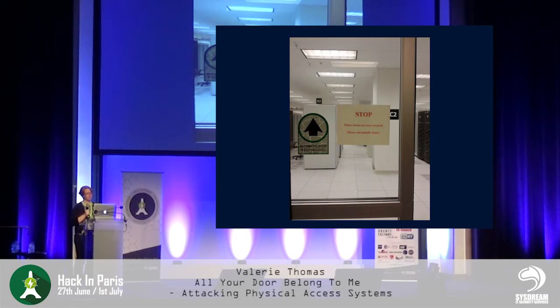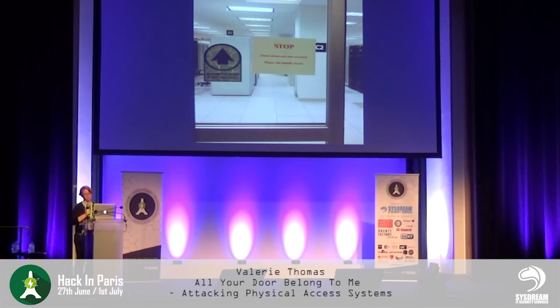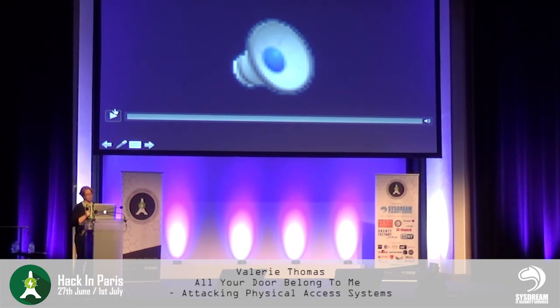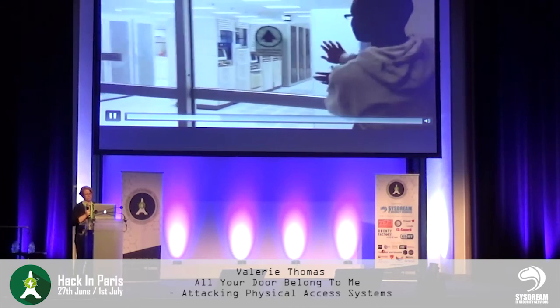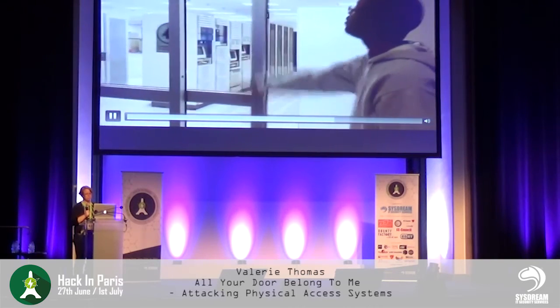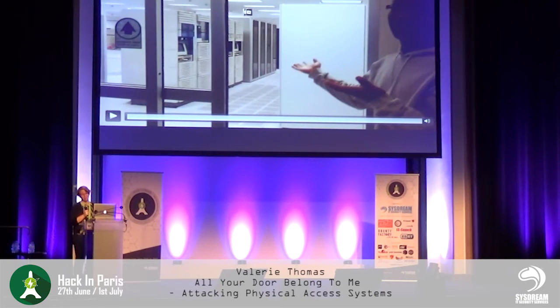We had a client that installed these types of doors on their pre-production data center because they thought it would be easier for the techs to get in and out with their carts and things without having to worry about holding the door. It's set up to comply with the fire code in the States, but they kind of forgot to make some adjustments to it. So you don't actually have to swipe to open it, you can just push it open. They were not amused. We thought it was great.